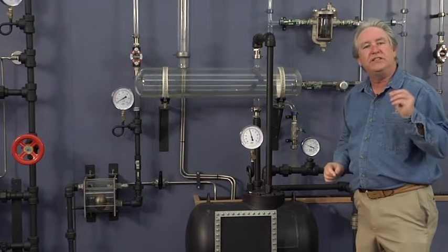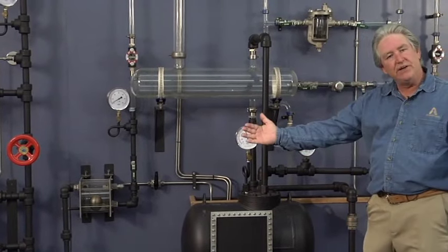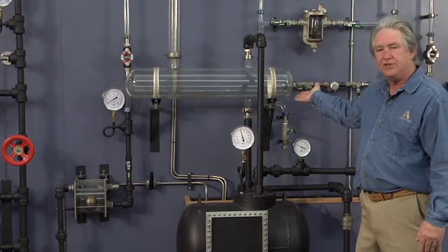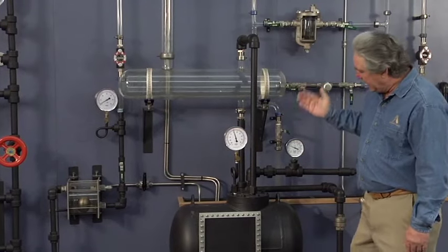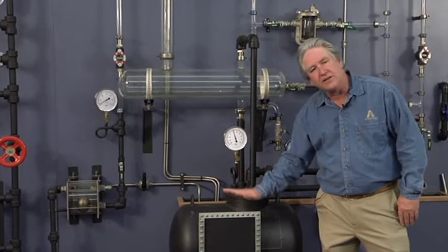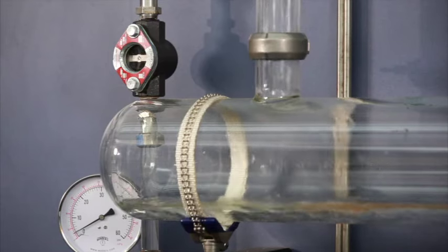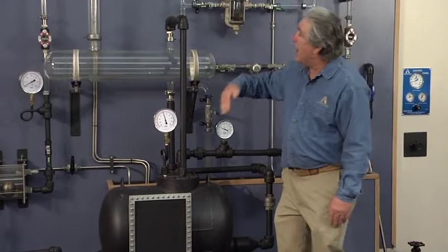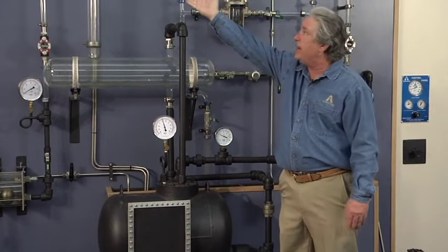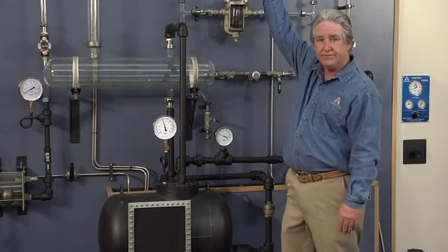But note this is very important. Why is it important for the reservoir on a pumping trap? Because even though we are now in the pump out cycle of the pump, which closed the inlet check valve, we're now still condensing the same rate of liquid in the heat exchanger.